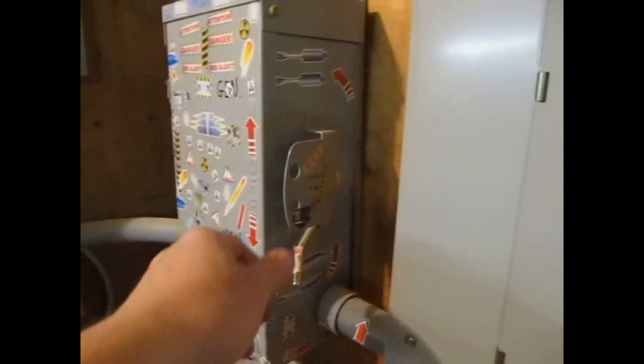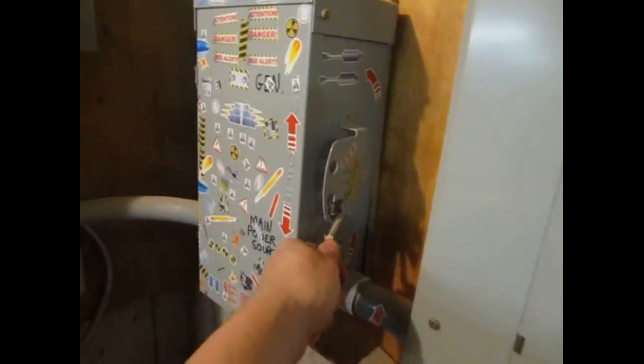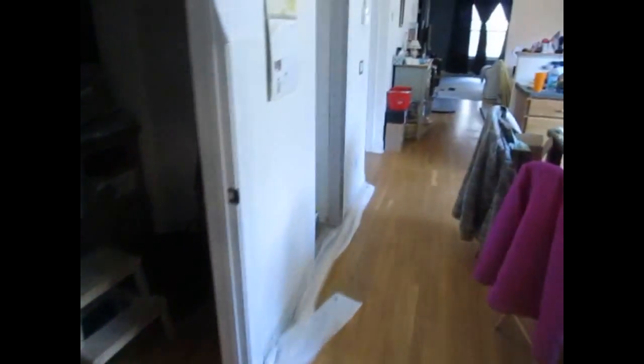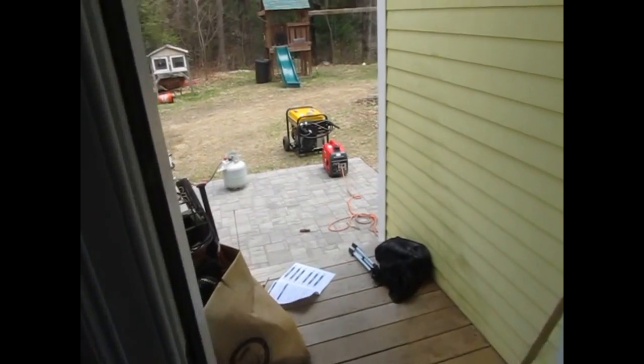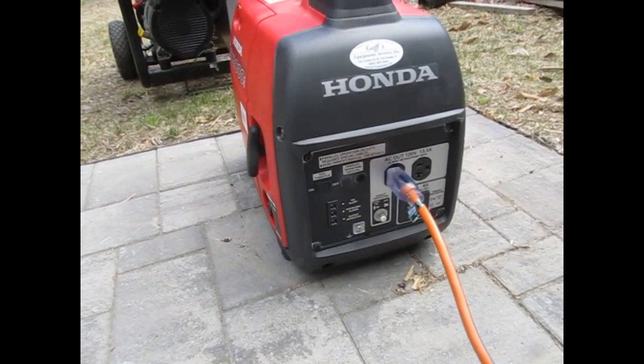Now I'm going to flip the switch. This is the transfer switch — this is what happens when you leave your kids alone with stickers when they're young. I flip the transfer switch and this takes this panel off the main panel, off of grid supply, and moves it onto the generator. I see light. I see no breakers trip. The fridge is on — that's a good sign. I can hear the freezer running. The alarm is coming back from trouble mode, so it's powered up. I can hear the generator — it's come off eco throttle and gone to high throttle mode. This works.